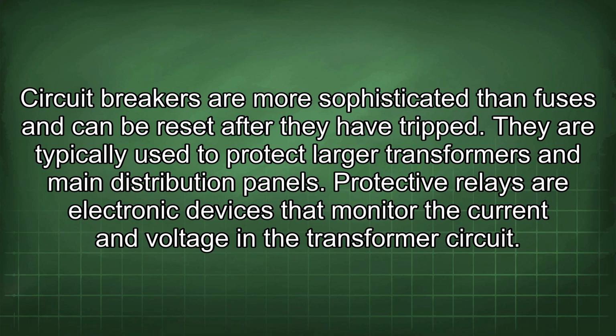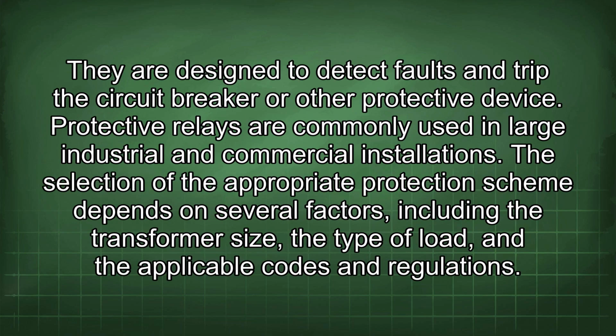Protective relays are electronic devices that monitor the current and voltage in the transformer circuit. They are designed to detect faults and trip the circuit breaker or other protective device. Protective relays are commonly used in large industrial and commercial installations. The selection of the appropriate protection scheme depends on several factors, including the transformer size, the type of load, and the applicable codes and regulations.